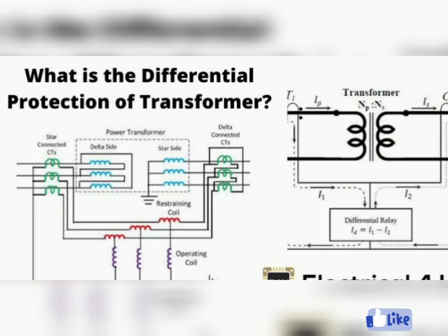Differential protection. This type of protection compares the current flowing into a transformer with the current flowing out of the transformer. If there is a difference between the two, it is an indication of a fault and the circuit is opened to protect the transformer.